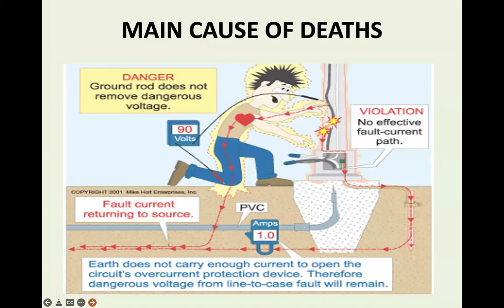When I say touching of a pole, this is the main cause of death, which happens because of touch potential. When a fault happens, it creates earth surface potential around that pole. When you touch it or come into the earth surface potential of that pole, there is a danger of touch potential as well as a danger of step potential. Proper protective device operation in minimum time can avoid that situation.